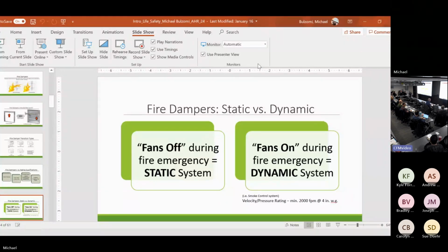I'll just tell you, I've been working for about 3 years now to remove the dynamic listing out of the UL directory. It can no longer be built to spec and is actually useless. And it's causing so many issues to you designers because you don't quite understand the intricacies of UL designs and the architects don't do their job. Anybody here an architect? Should have asked that first. Architects don't do their job. They don't specify the floor ceiling assembly. They just give you a set of plans and then you go in and do your thing. And then they go, oh, by the way, here's the floor ceiling assembly. And it changes everything you've done on your damper. Leave it at that. Somebody pull me out. I'm going to keep going. All right.